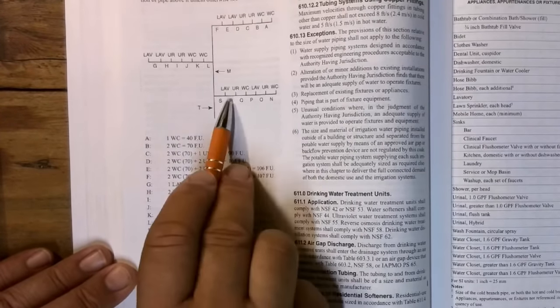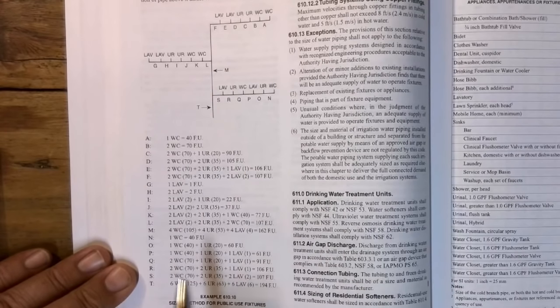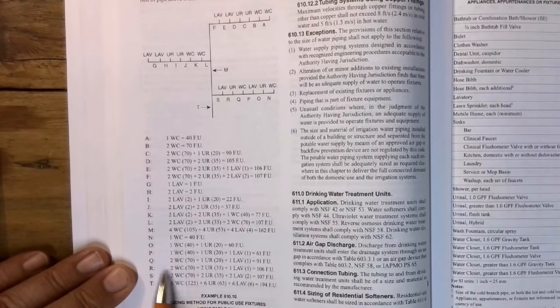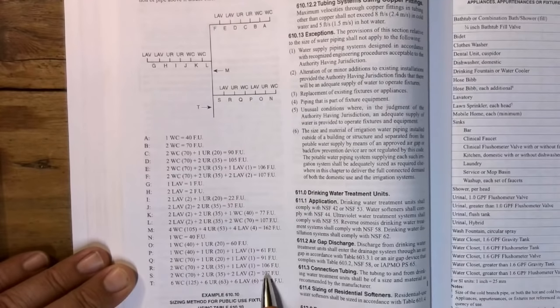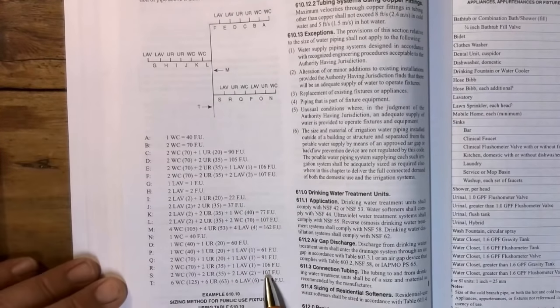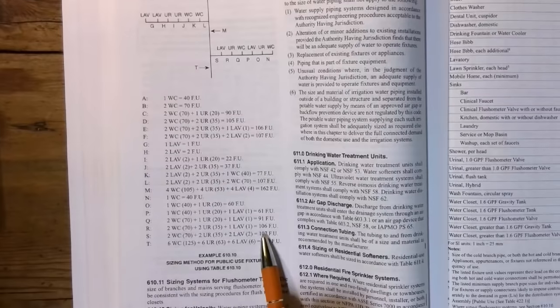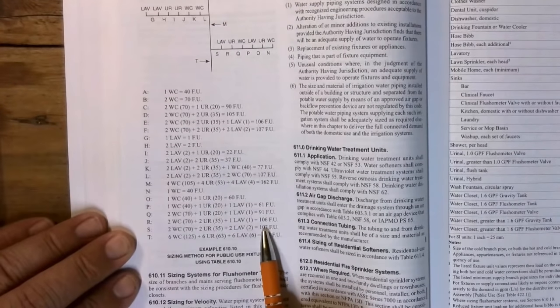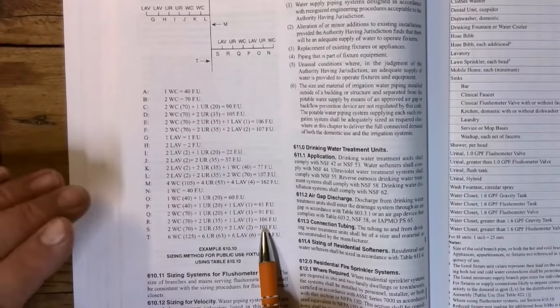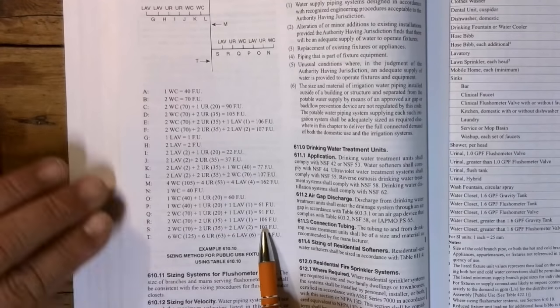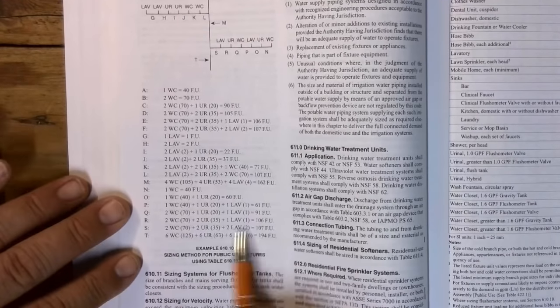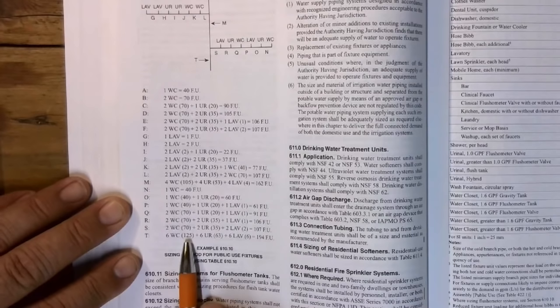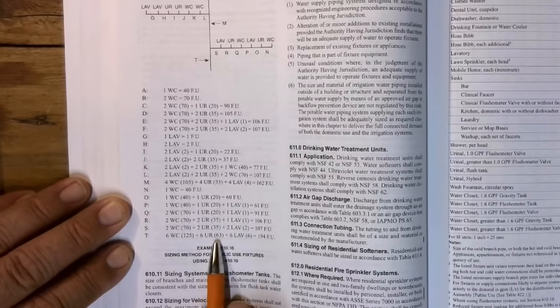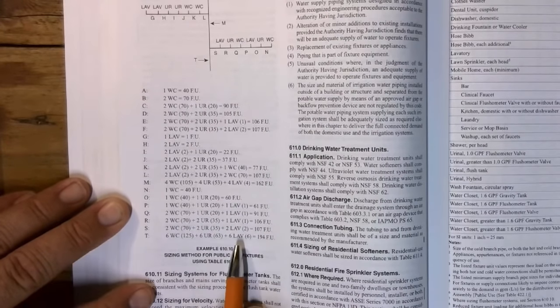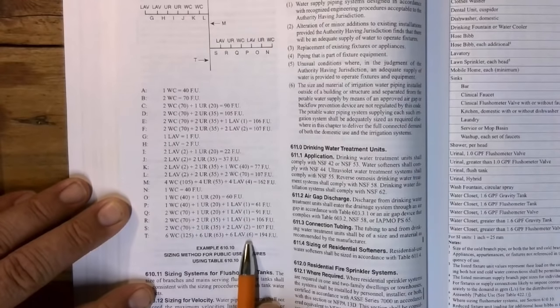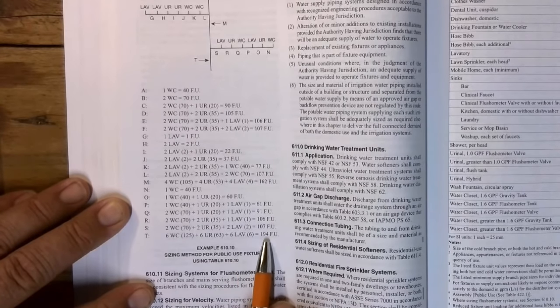Then you got this one, decreasing order again. It's kind of mixed and matched all the way to S. S, you get 107 fixture units. Makes sense, right? But you go to T. So now we have a total of six water closets for 125 fixture units, six urinals for 63 fixture units, six lavs for six fixture units, equaling out 194 fixture units.